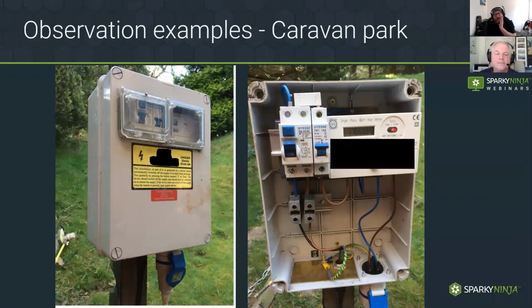All right, yeah, so we do some work in caravan parks, and we had a couple of images recently from these. This is a very typical caravan park hookup point - 16 amp socket, you can see there's a 16 amp overcurrent device, B type, and there's an RCD. Obviously regulations require individual protection for these. There's no information here on the earthing system, but it's most likely not going to be a PME, hopefully. Hope.